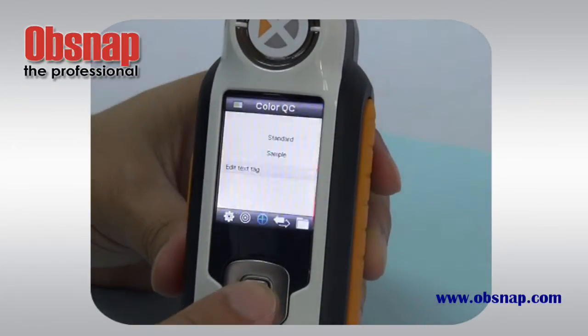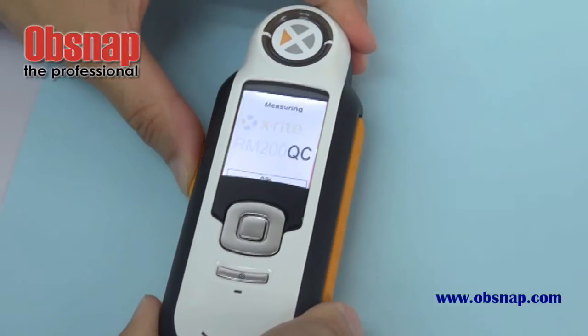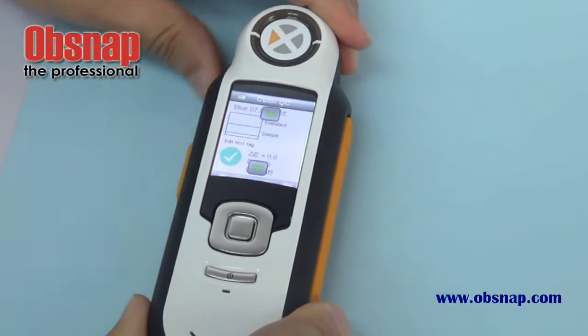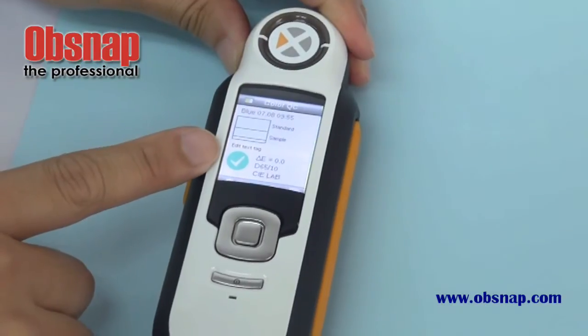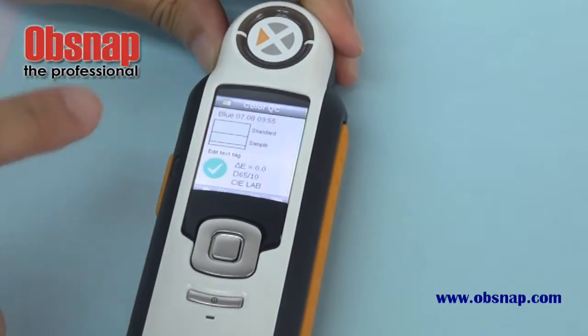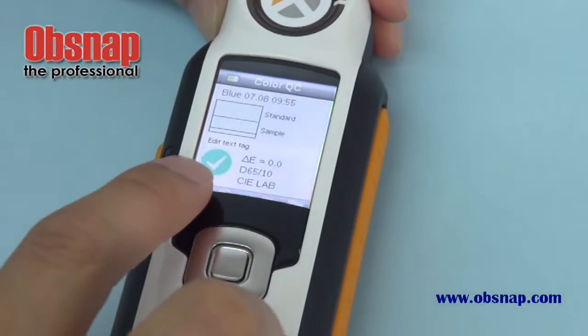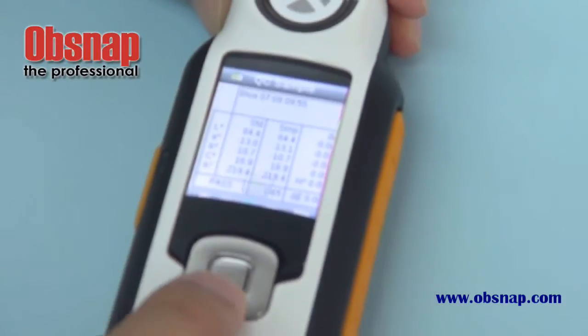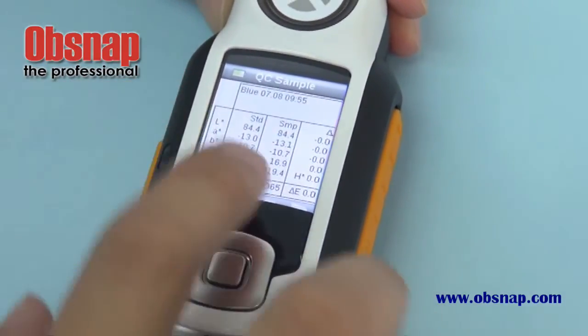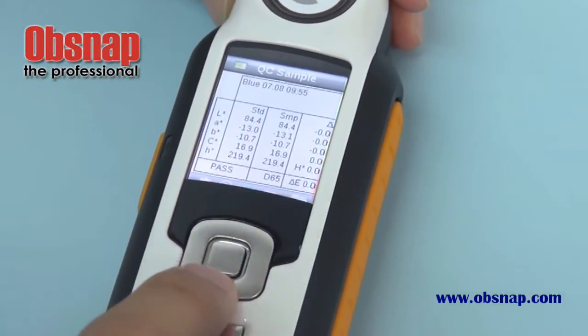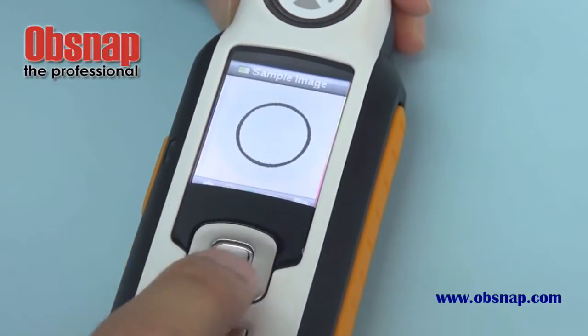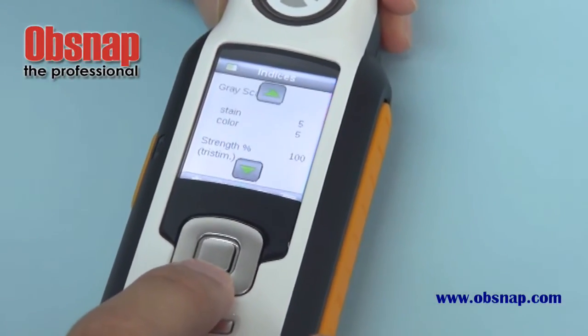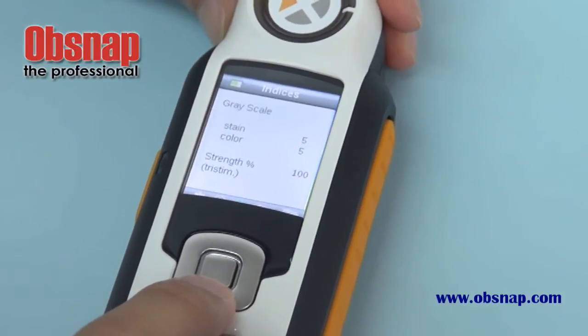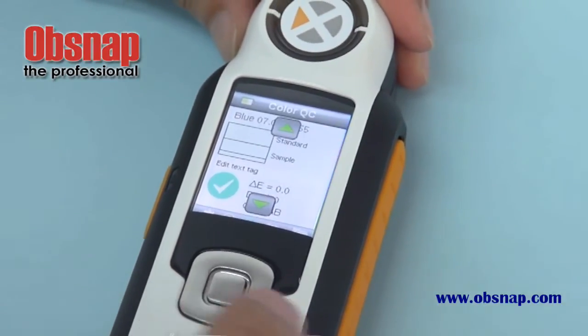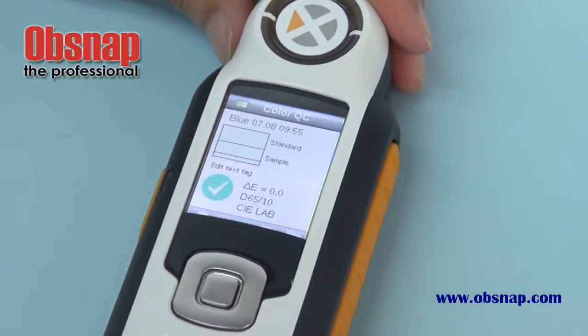We do the measurements. So now once we measure on our sample, the unit will automatically compare with our standard, which is already saved into our RM200QC. And the result is pass because delta E is perfect, 0.0. Then we can view all the readings, standard and sample readings comparison, all is 000. And then we can view the graph, plot graph, and then the grayscale, stain color, and strength of the color. So we can view all the data from the screen here.